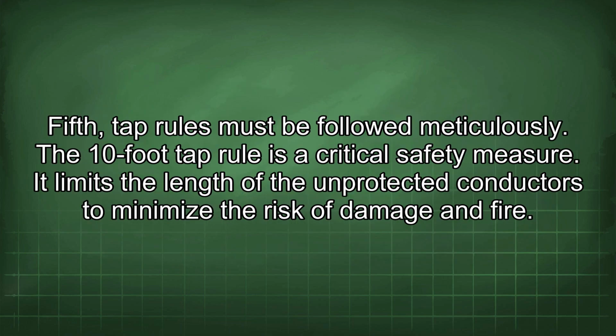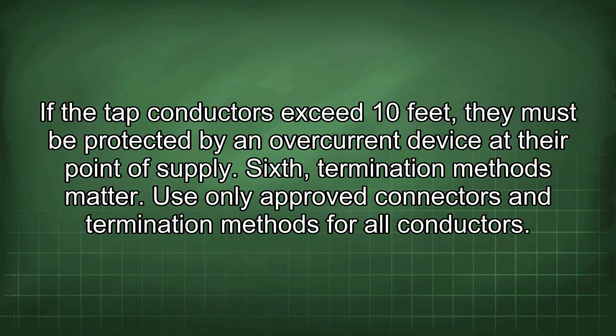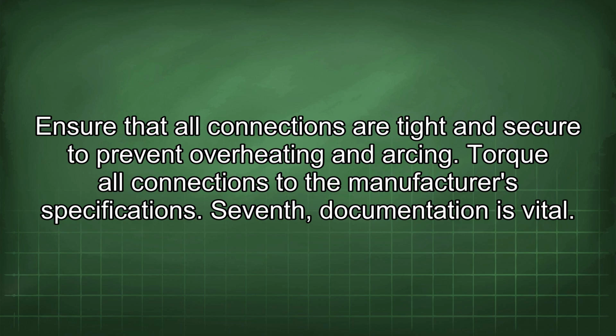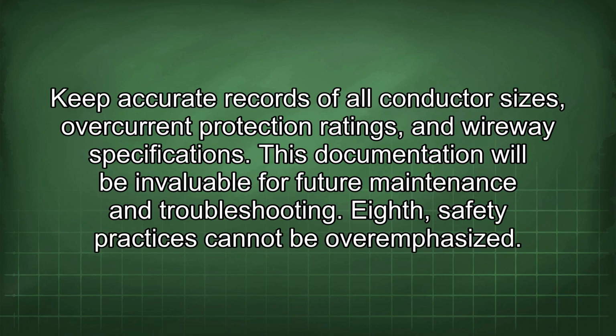Fifth, tap rules must be followed meticulously. The 10-foot tap rule is a critical safety measure. It limits the length of the unprotected conductors to minimize the risk of damage and fire. If the tap conductors exceed 10 feet, they must be protected by an overcurrent device at their point of supply. Sixth, termination methods matter. Use only approved connectors and termination methods for all conductors. Ensure that all connections are tight and secure to prevent overheating and arcing. Torque all connections to the manufacturer's specifications. Seventh, documentation is vital. Keep accurate records of all conductor sizes, overcurrent protection ratings, and wireway specifications. This documentation will be invaluable for future maintenance and troubleshooting.